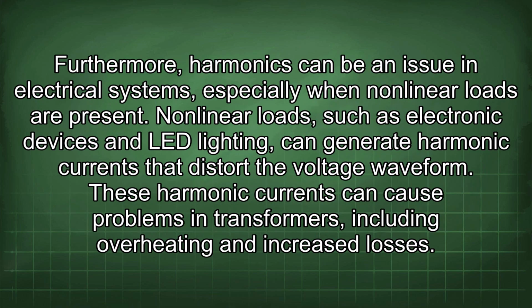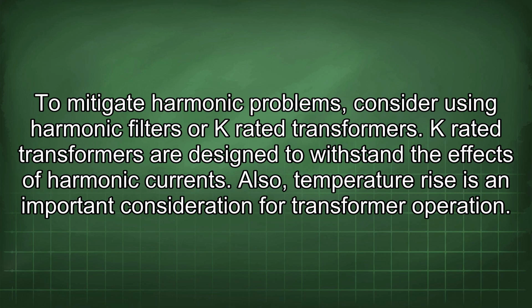Furthermore, harmonics can be an issue in electrical systems, especially when nonlinear loads are present. Nonlinear loads, such as electronic devices and LED lighting, can generate harmonic currents that distort the voltage waveform. These harmonic currents can cause problems in transformers, including overheating and increased losses. To mitigate harmonic problems, consider using harmonic filters or K-rated transformers. K-rated transformers are designed to withstand the effects of harmonic currents.